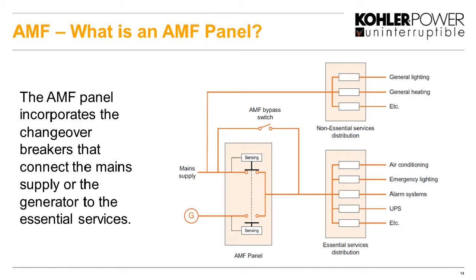So inside the AMF panel, you can see this drawing here, a schematic of the generator and main supply coming in. So the AMF panel has voltage and frequency sensing on the generator and the main supply. And then we can see here, the way it's cabled up, that the main supply also feeds non-essential equipment that will not be fed from the generator. Okay, so when the generator is on load, it'll be feeding the UPS, air conditioning, emergency lights and alarm systems. But in this case, it won't be feeding the general lighting and general heating. So that is dependent on what's critical in your installation, and also determines the size of the generator as well, depending on what the customer decides is essential load.